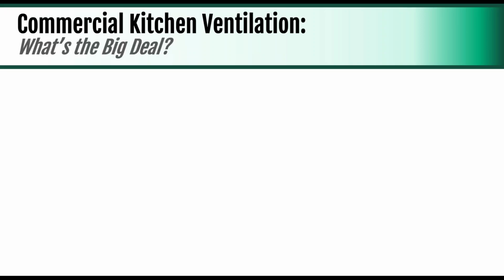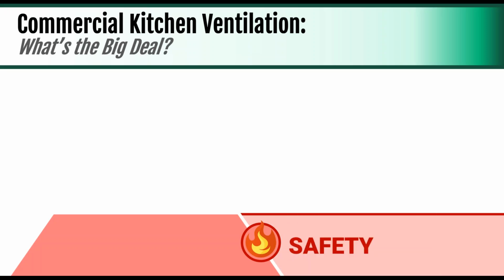So commercial kitchen ventilation, what's the big deal with it? If you're familiar with it at all, you'll know there are a ton of codes around it, and that's because you're playing with grease. The commercial kitchen typically has lots of appliances that put off grease. A lot of them, such as fryers, have grease. And before some of these codes, and even after some of these codes, some of the more dangerous building fires originated in kitchens, just because it's such a big source of heat and flammable components.